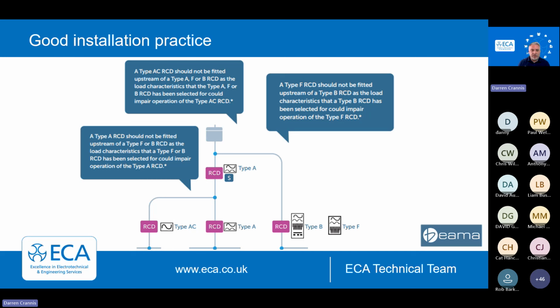So if you've got installations that are predominantly domestic and you put a renewable distribution board in there, maybe that's becoming a more common thing. If it's on a TT, you won't be able to put that downstream of a type A. You may have to go type B or above for your main switch, or you might have to split the tails. So importantly, the way type Bs and type Fs work is completely different, but they like being on their own. And they have that higher threshold, that 10 milliamp and above. They also have that ability to disconnect if there is a DC fault present, unlike the A and the ACs, which will just tolerate it or may not even function at all. So it's important that we split this down.